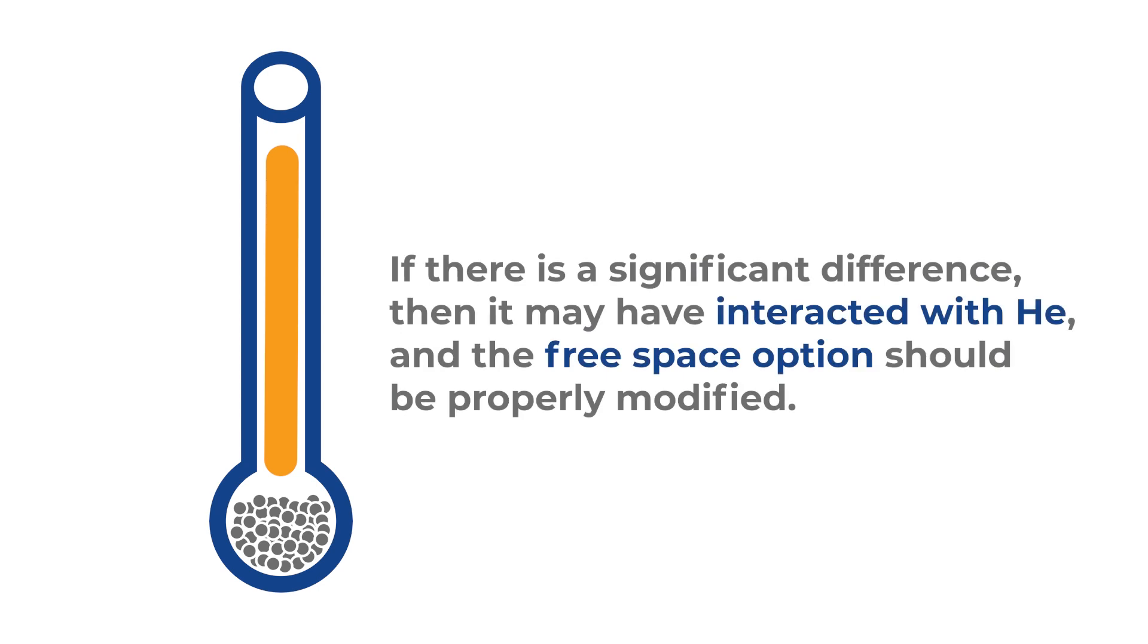If there is a significant difference between the two, then the sample may have been interacting with helium and the free space option should be properly modified.